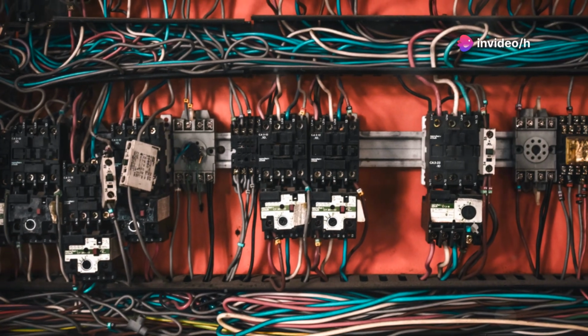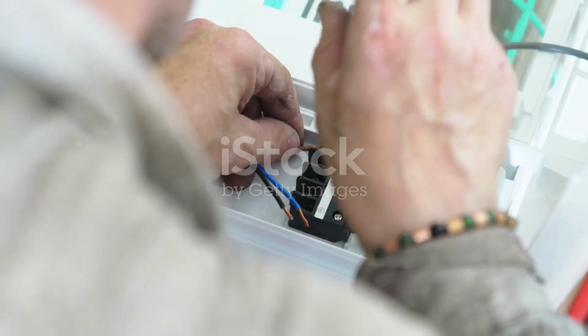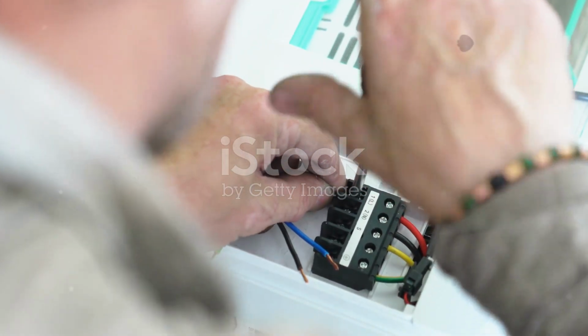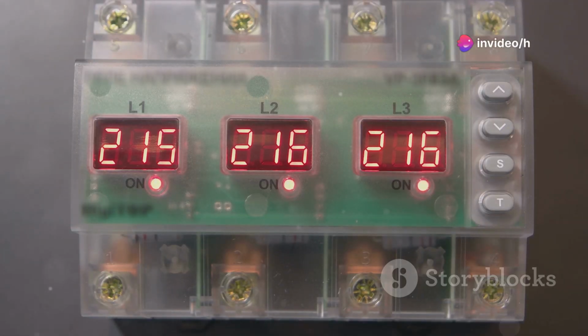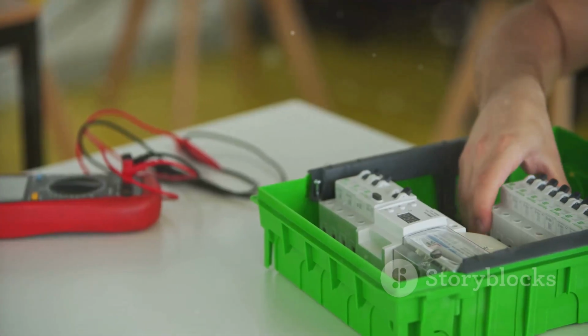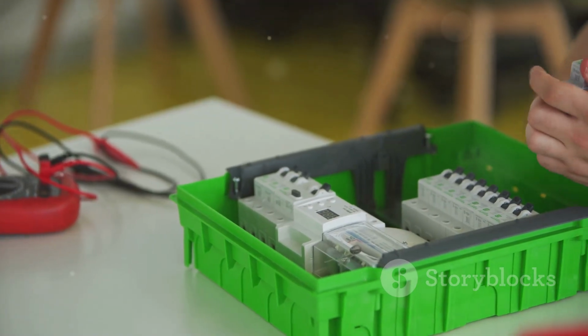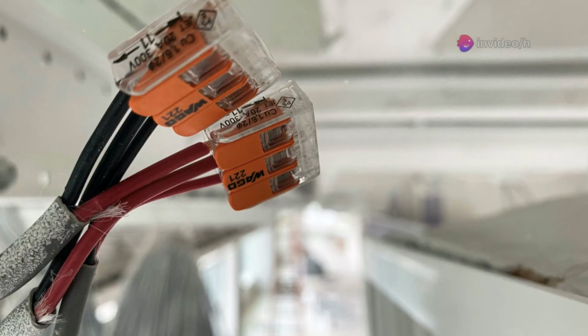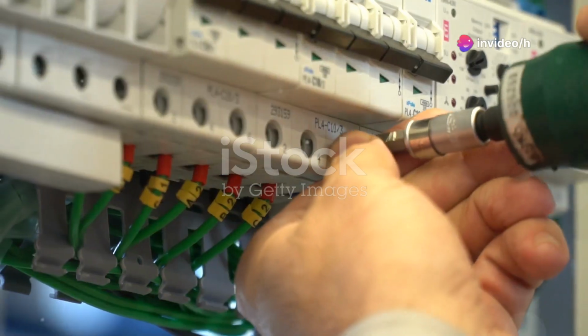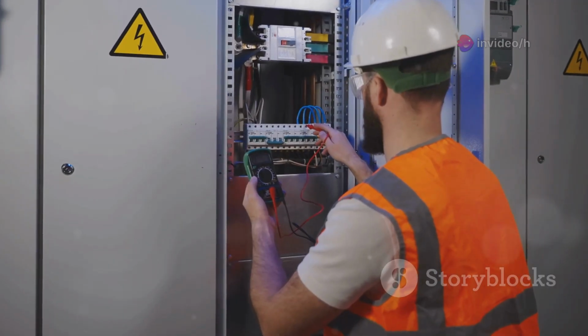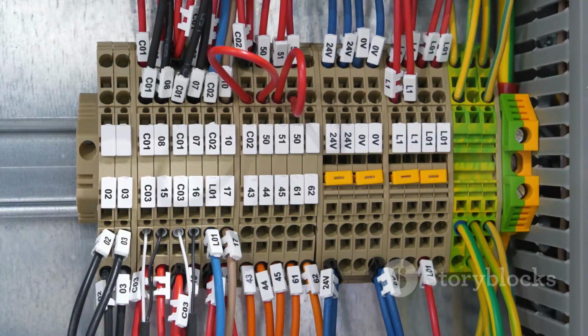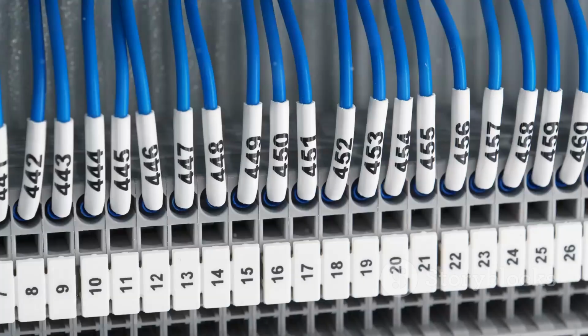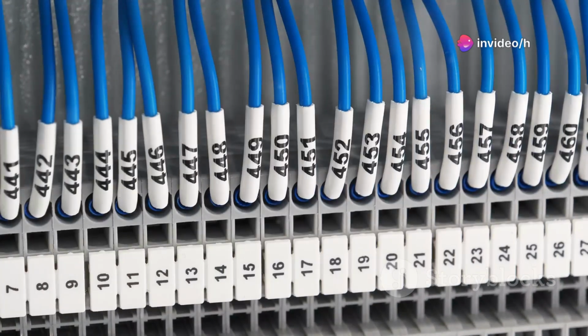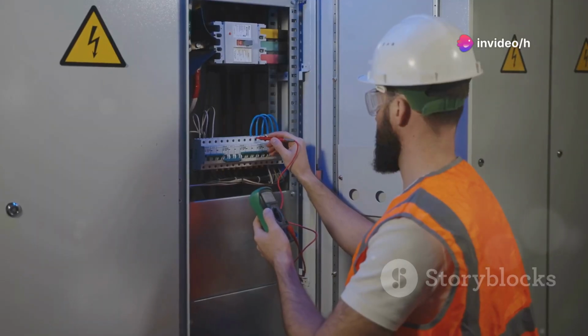Next, single-phase outputs. Let's keep it balanced. Now, connect the 8 single-phase motors, workhorses of your facility. Distribute them across the 3 phases to balance the load. 3 on phase 1, 3 on phase 2, 2 on phase 3. Each motor gets a hot wire from its MCB and controller, plus neutral and ground. Use a neutral bus bar for tidy, secure connections. Correct wire size is critical. Undersized wires are a fire risk. Tighten all connections and avoid stray strands. Label each circuit clearly. Review your work. Balance loads, solid connections, clear labels. Fundamentals matter. This is how you build for longevity.